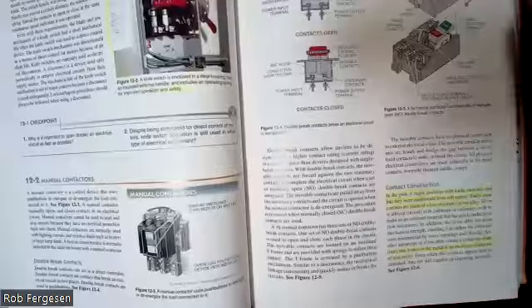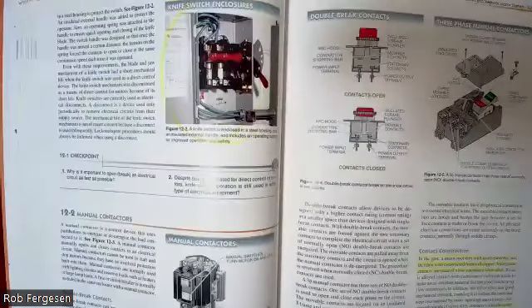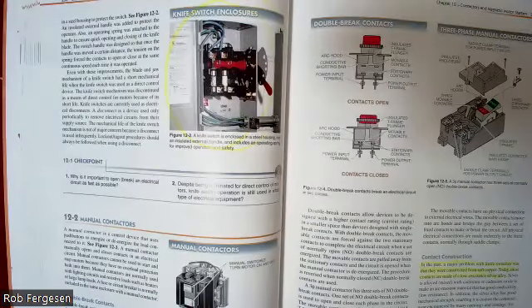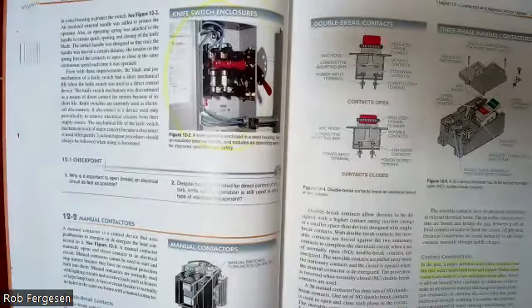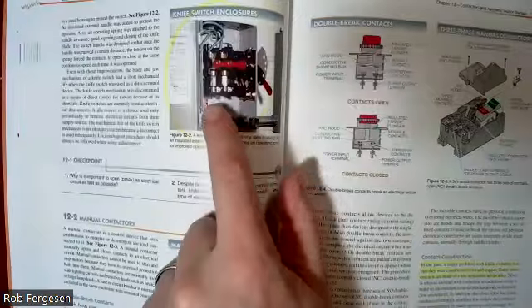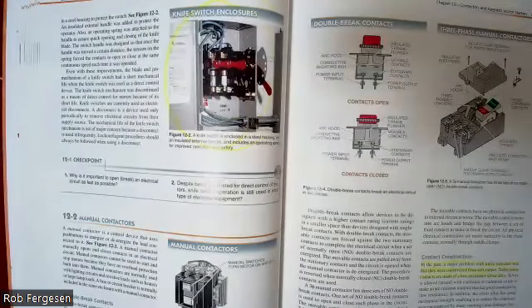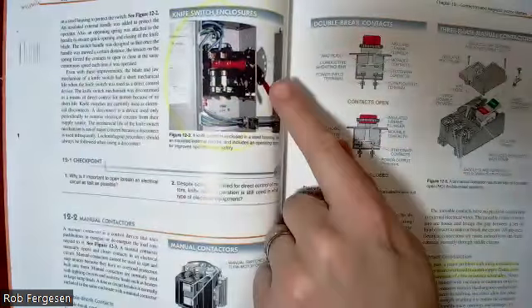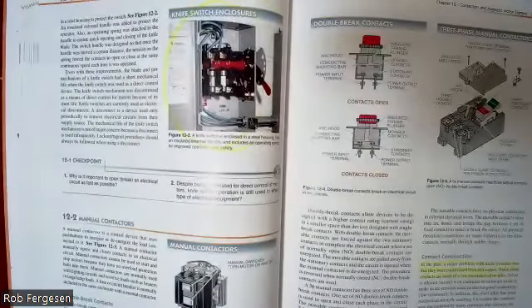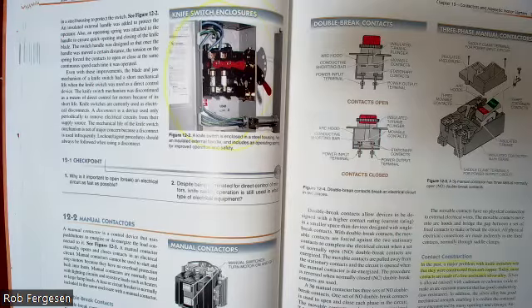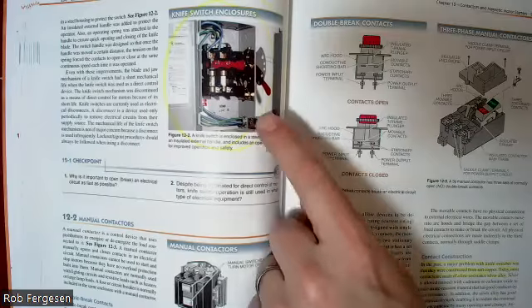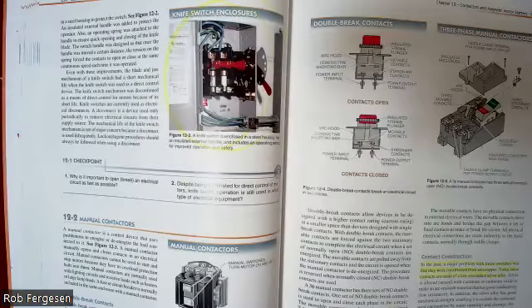That's your classic switch. The reason why we still include that today is on the top of page 238, and I've highlighted this, is a picture of what should be familiar to everybody, which is a disconnect box. When you pop open that cover on a disconnect box, you're going to see usually some fuses, 2 or 3 fuses, depending whether it's single phase or 3-phase, and you're going to see a little rotating knife switch. So when you run this lever down to open or close that connection, you're going to see these little knives, little poles swing down and create a connection, just like an old school knife switch. Now, of course, these are much safer because they're inside of an enclosure. The enclosure has different techniques to keep you from doing that while it's open. And so those are little knife switches in there. So that's useful to know.